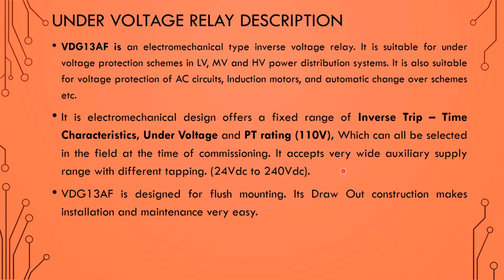It accepts a very wide auxiliary supply range with different tappings. That means this relay needs an auxiliary power supply, and it can accept 24 volt DC to 240 volt DC with a particular value of tapping. That means any DC voltage above 24 volt and up to 240 volt we can use for this relay.